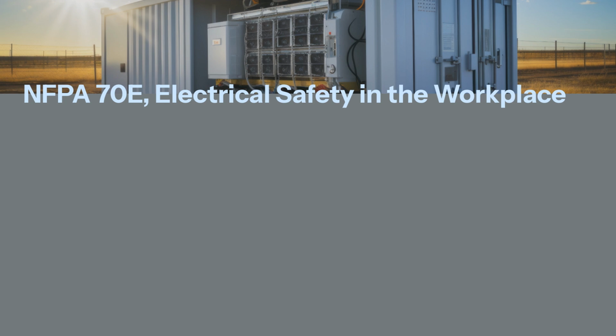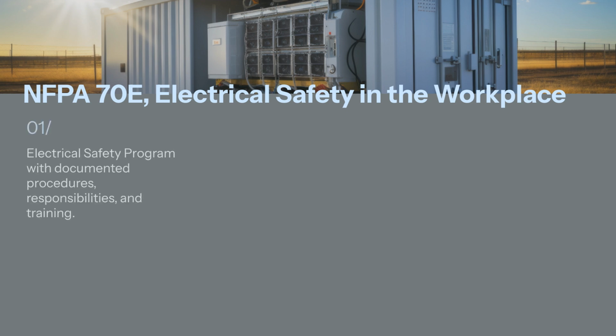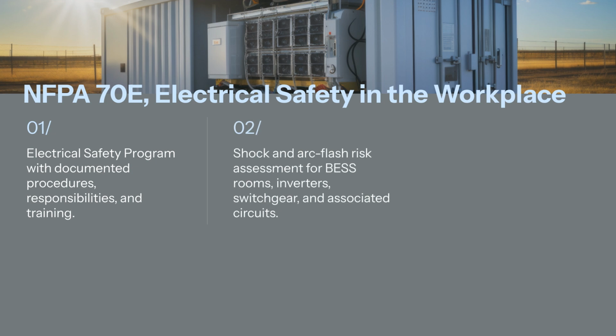Standards and regulatory framework. NFPA 70E, Electrical Safety in the Workplace. NFPA 70E defines safe work practices to protect workers from electric shock, electrocution, arc flash, and arc blast during installation, operation, maintenance, and demolition of electrical equipment. Key implications for battery storage systems include an electrical safety program with documented procedures, responsibilities, and training, and shock and arc flash risk assessments for battery and energy storage system rooms, inverters, switchgear, and associated circuits.